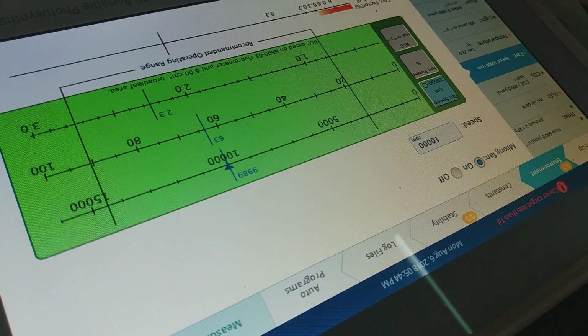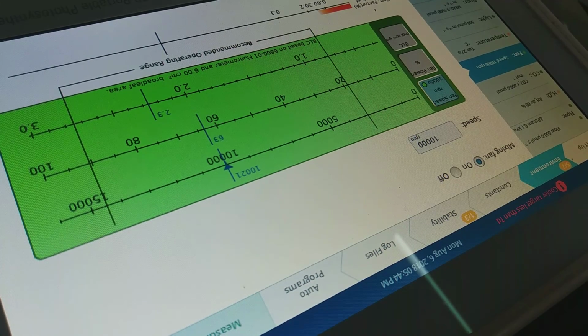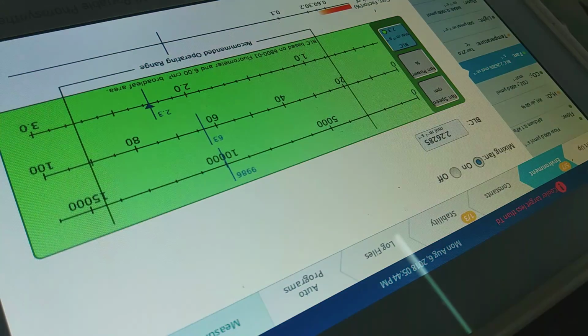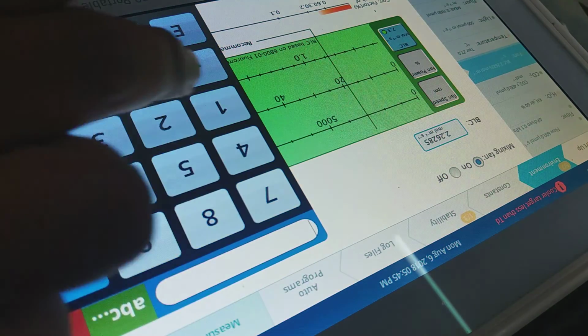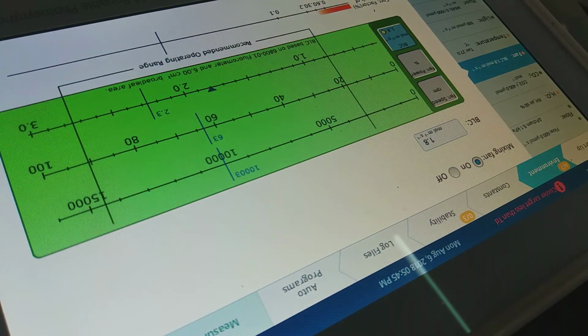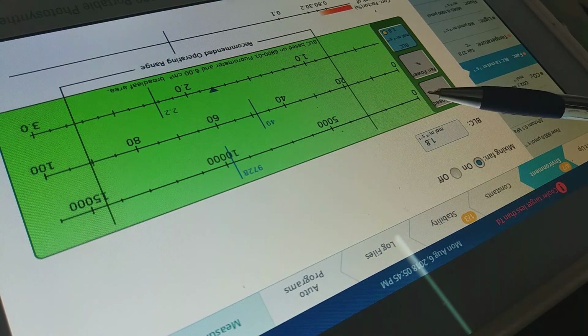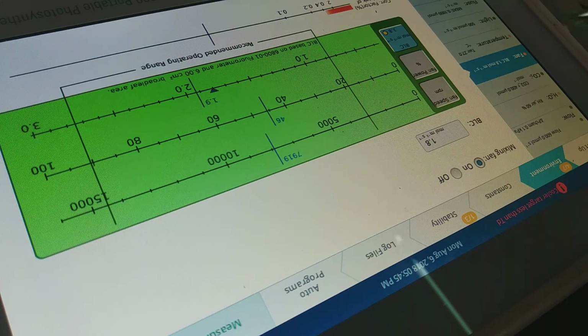If you choose to set your boundary layer to a specific value, this will change. For example, set the boundary layer to 1.8. Try to set it, and watch what happens to the fan speed. See, it overrides the fan speed.